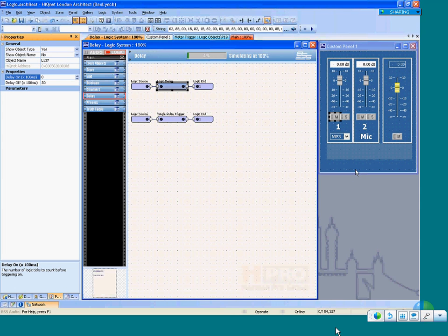If the CPU on that blue box is busy doing something else, it might not get around to the logic until 103 milliseconds, 104 or 5 milliseconds. If a great big humongous serial command comes in right at the wrong second and it's triggering a bunch of presets, it could be 108, 110 milliseconds before the device gets around to it.